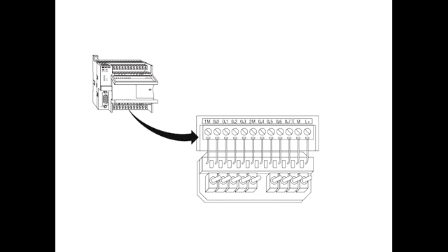Testing a program. Once a program has been written, it needs to be tested and debugged. One way this can be done is to simulate the field inputs with an input simulator, such as the one made for the S7-200. The program is first downloaded from the programming device to the CPU. The selector switch is placed in the run position. The simulator switches are operated and the resulting indication is observed on the output status indicator lamps.